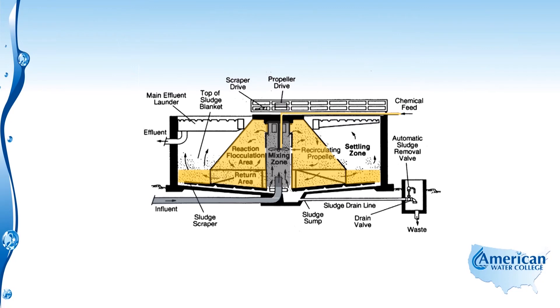Coagulation happens in the mixing zone and flocculation happens in the outer areas of this cone. The water then flows underneath this reaction cone and forms a sludge blanket at the bottom of the clarifier. Any water leaving this center chamber has to go through the sludge blanket and flow upward — that's where the phrase 'upflow clarifier' comes from.